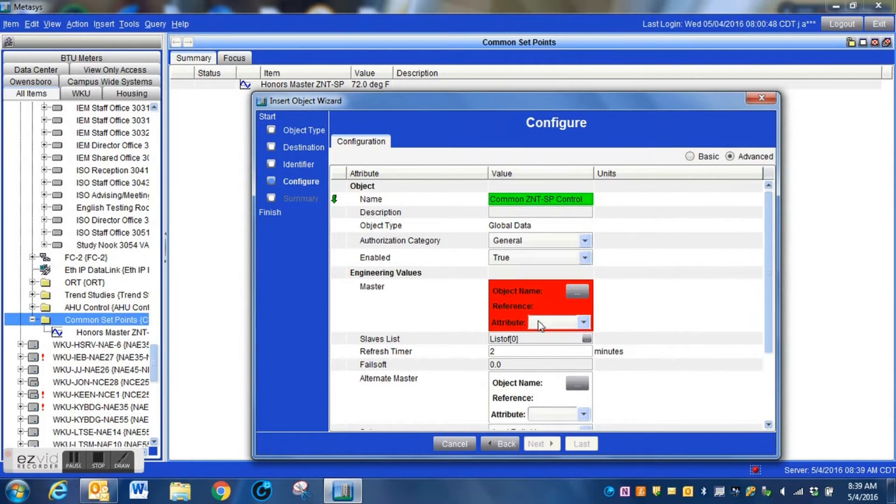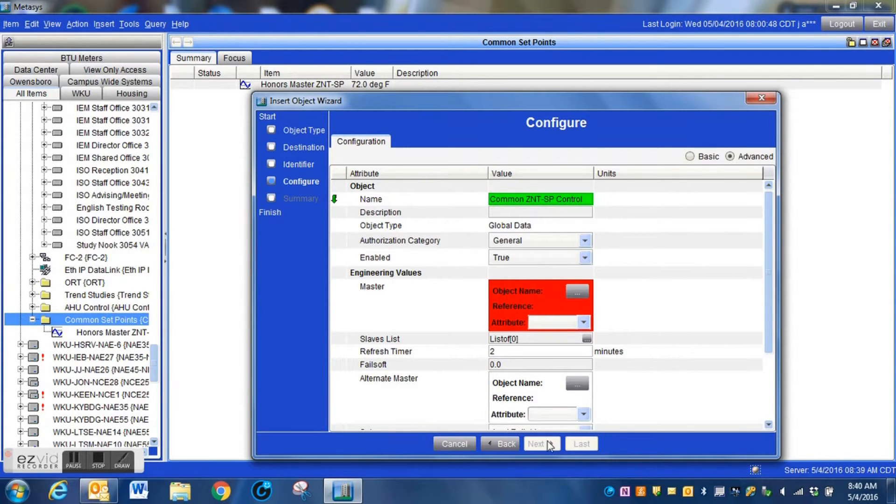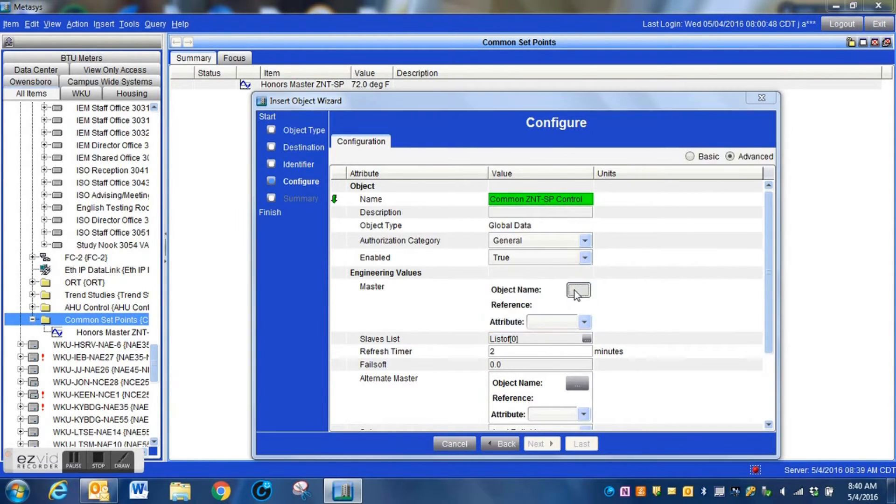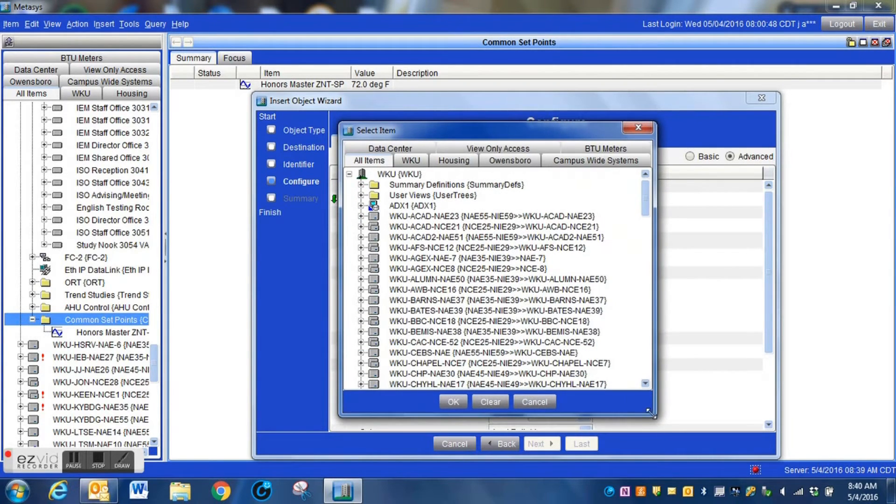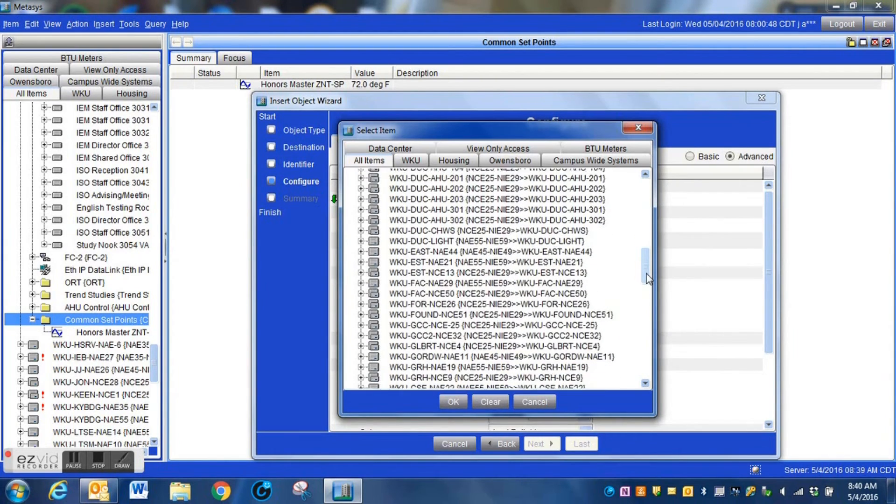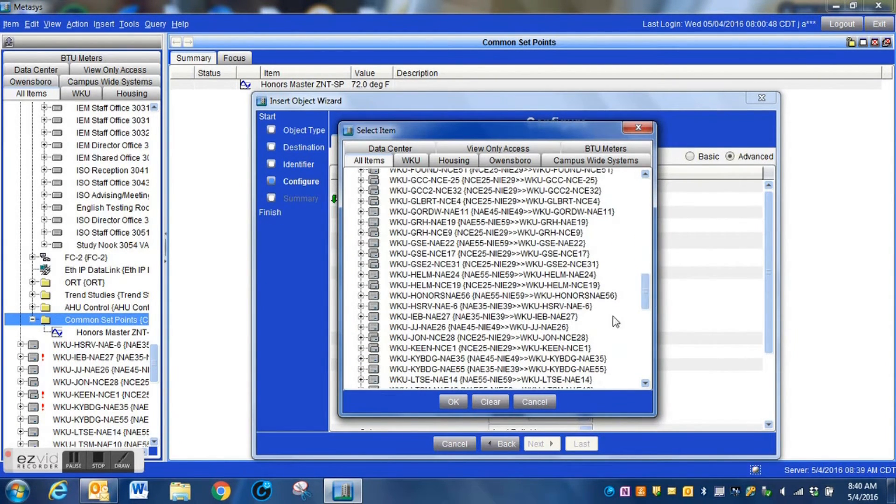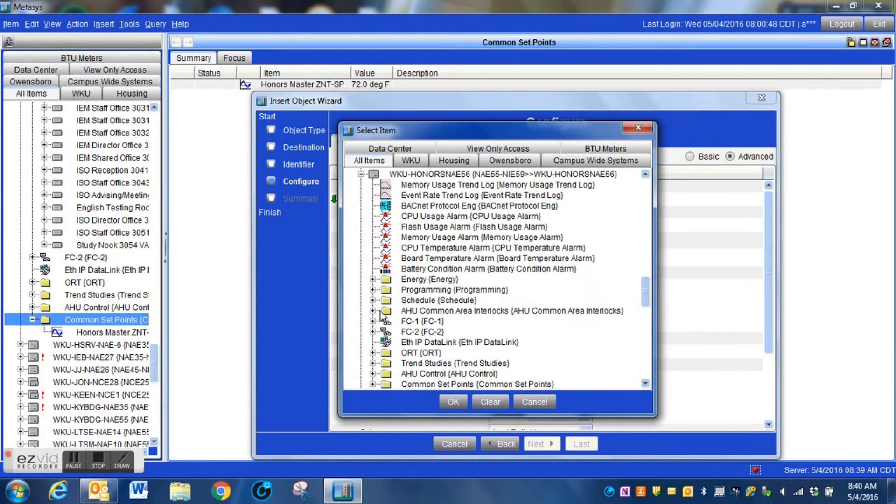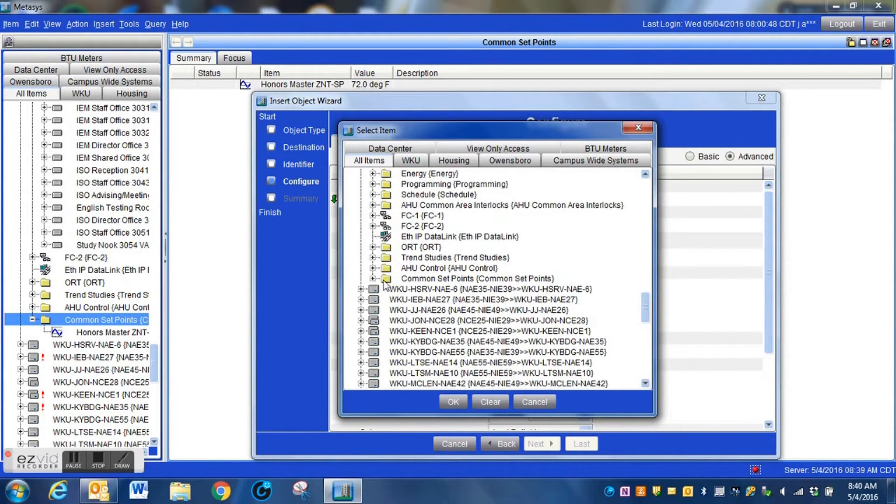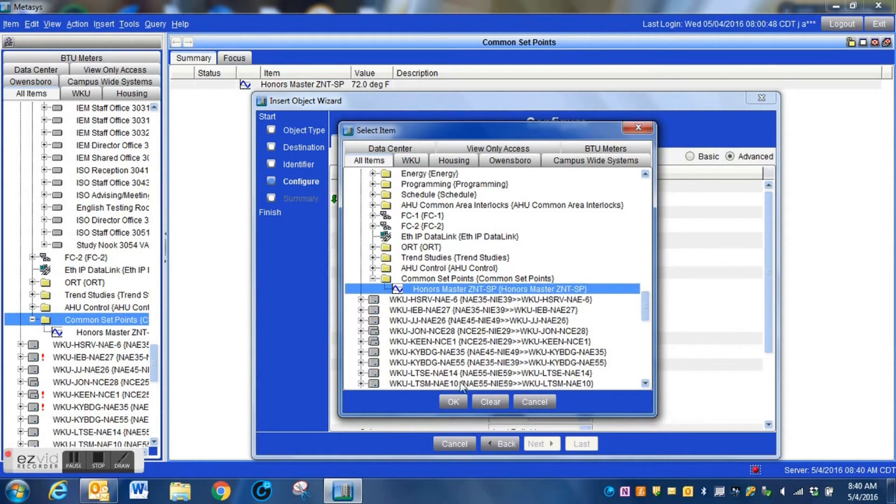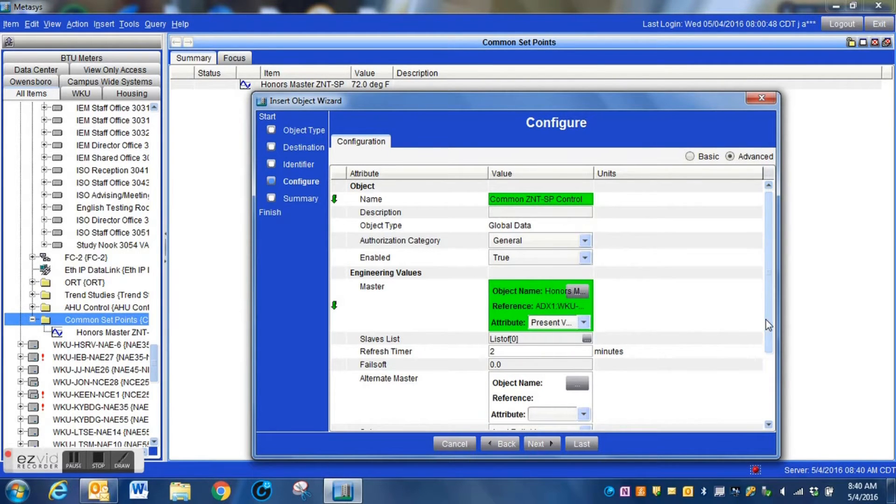You'll notice here in this configuration screen, this red box. This is the master point that this global data object is going to be looking at. It has to know where it is to look for its information. So we're going to click this box, we are going to expand out our network, we're going to drill down, and we are going to go to where we put the analog value that we created, which is in that same folder. That is going to be the information that we're going to be passing to all of the devices on the slaves list.